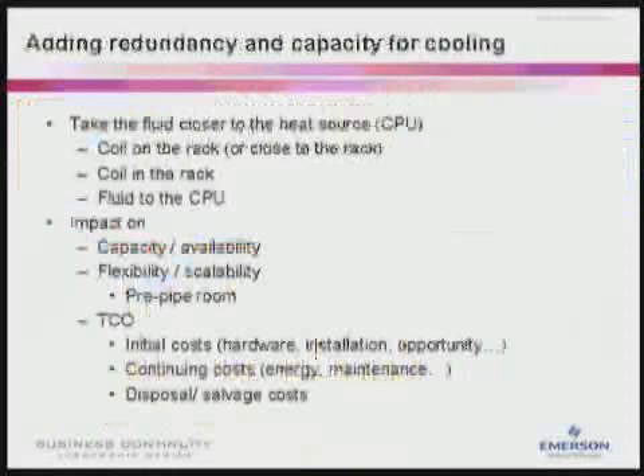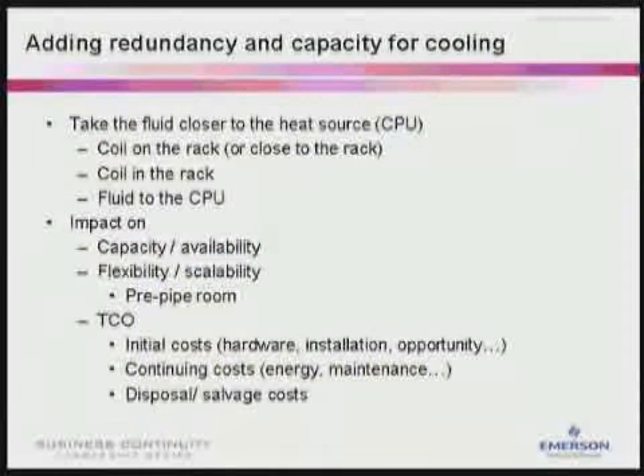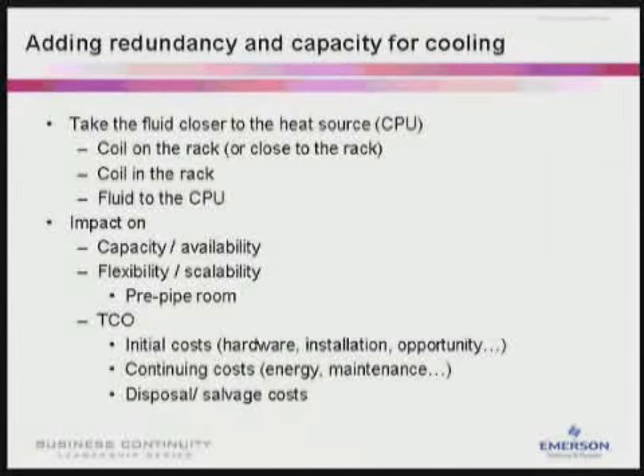Adding redundancy for cooling can be accomplished with the addition of local cooling. You want to take the fluid closest to the heat source, either through coils on the rack, coils in the rack, or fluid directly to the CPU. It has a positive impact on capacity and availability, as well as scalability and total cost of ownership.